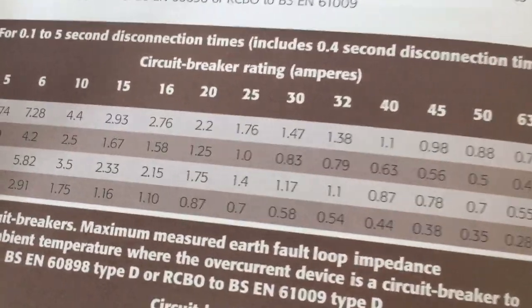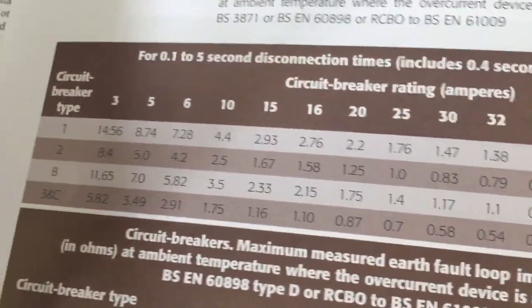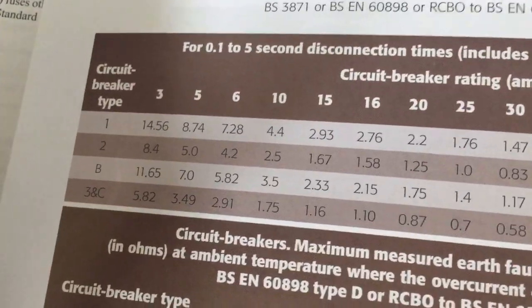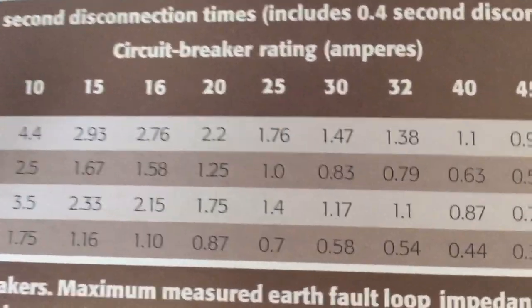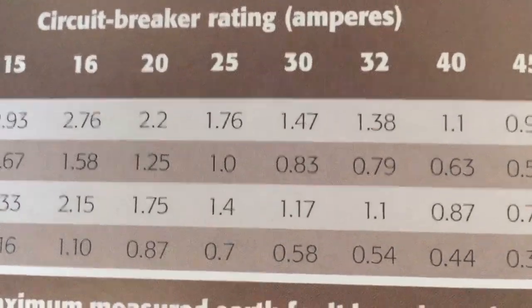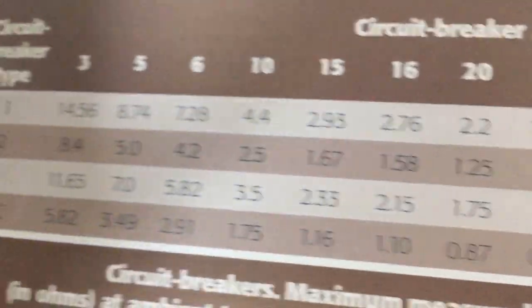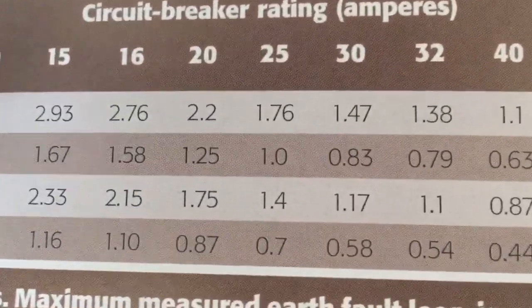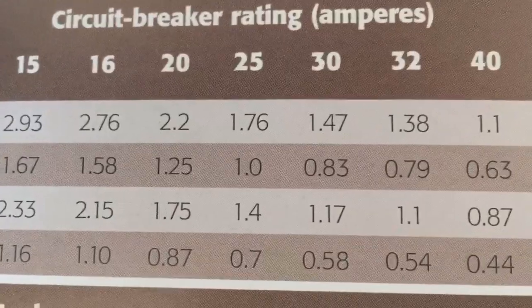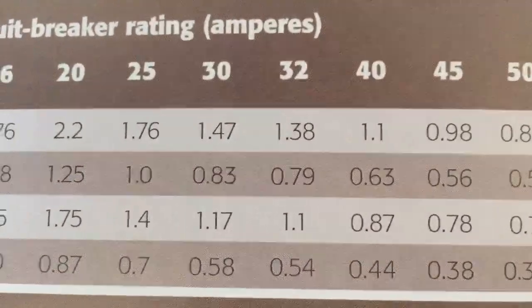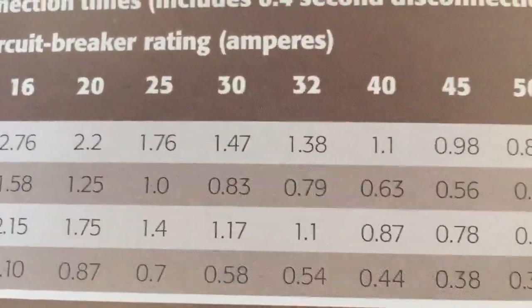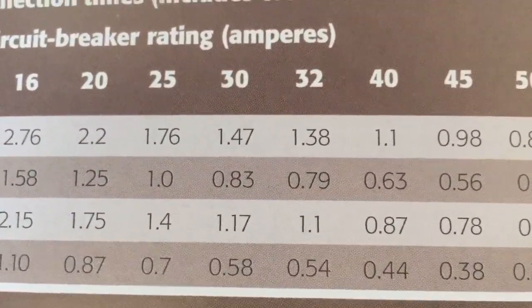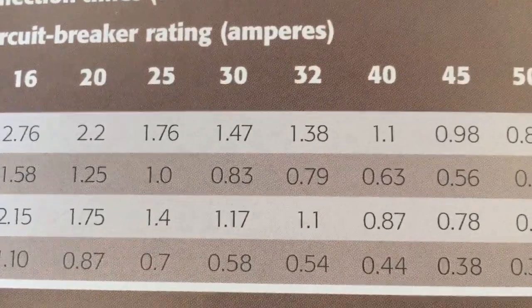The 80% values — the ones we directly compare with — are in the On-Site Guide and GN3. If we look in for a B-type breaker, we can see B-type breaker 32 amps, which is what's protecting the circuit, and we've got 1.1Ω. So in this particular test, 1.1 is the figure to beat.